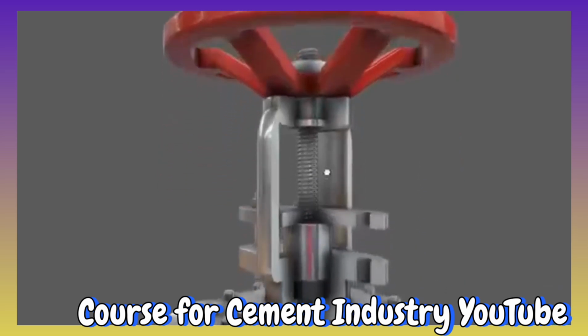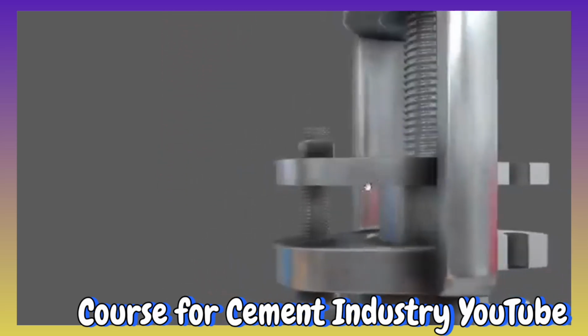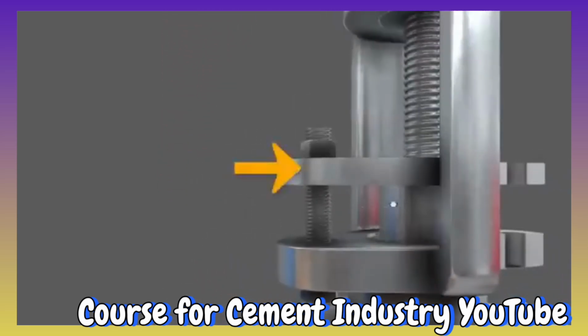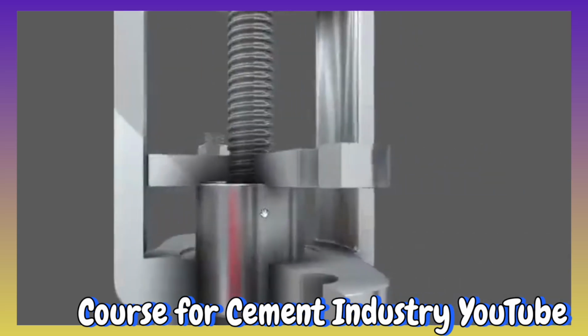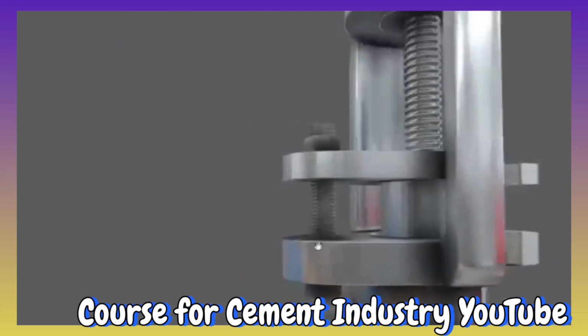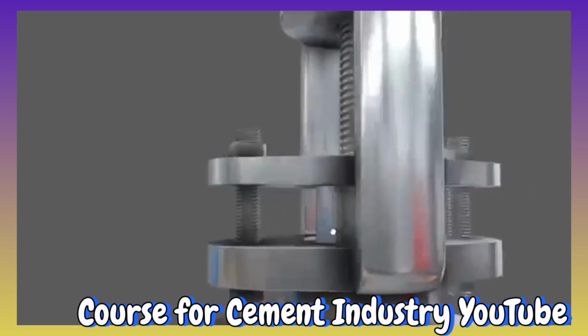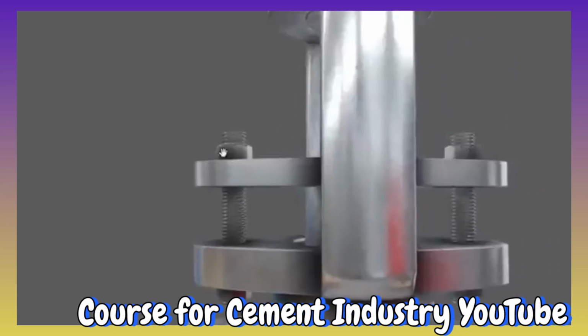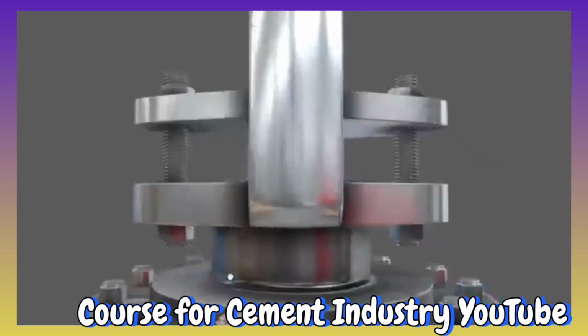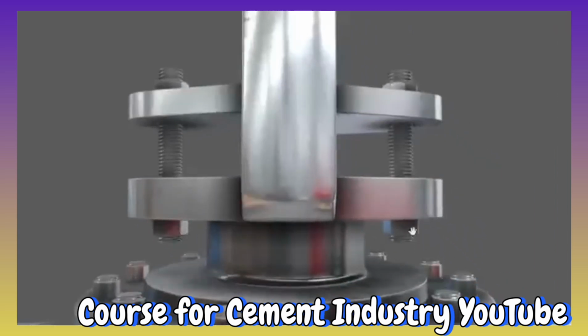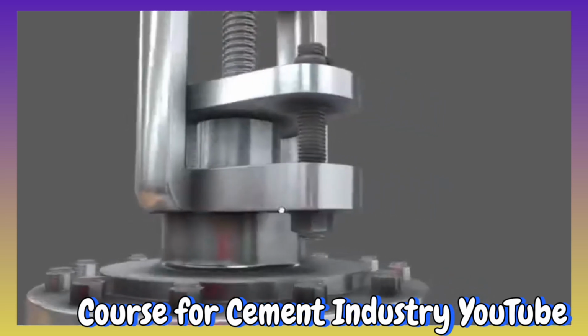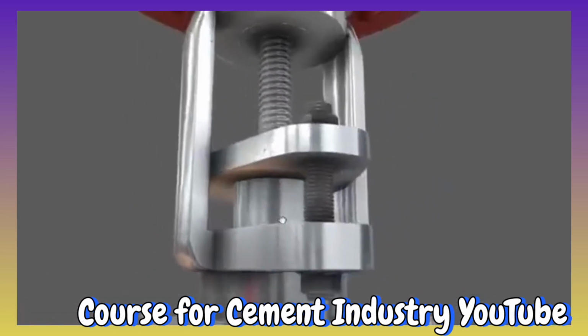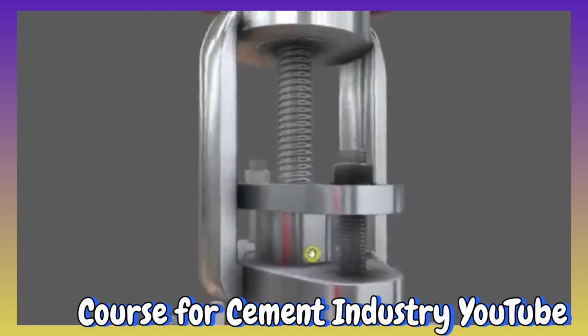We have here a follower, that is this metal plate here, and this piece. And if we were to tighten, let's just go to a full view. If we were to tighten the nuts here on the left hand side and on the right, and the same on the bottom side, then we would actually force the follower to press down on the packing gland, and this would tighten the seal between the bonnet and the stem.